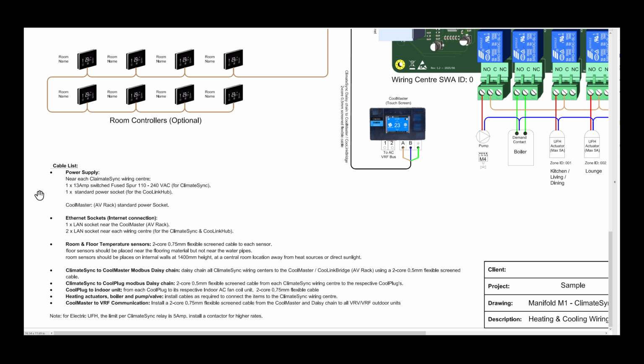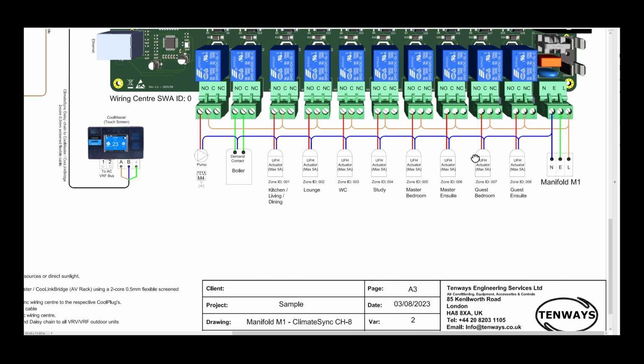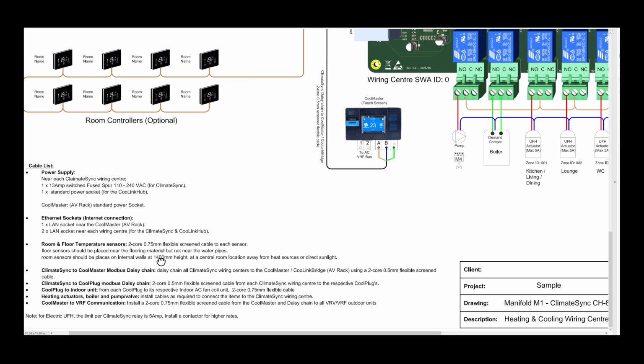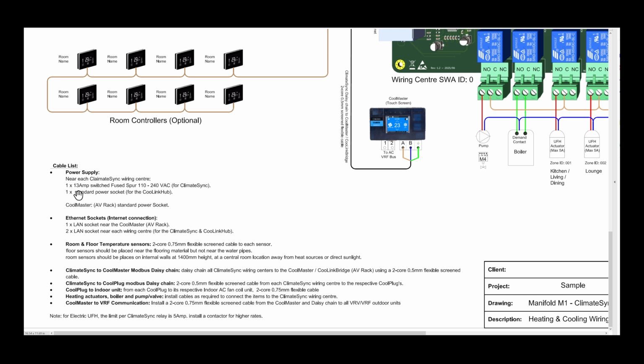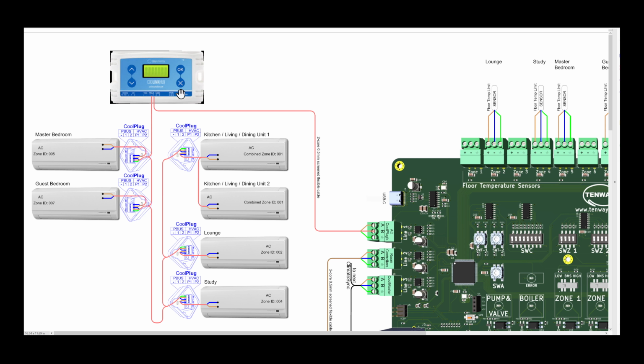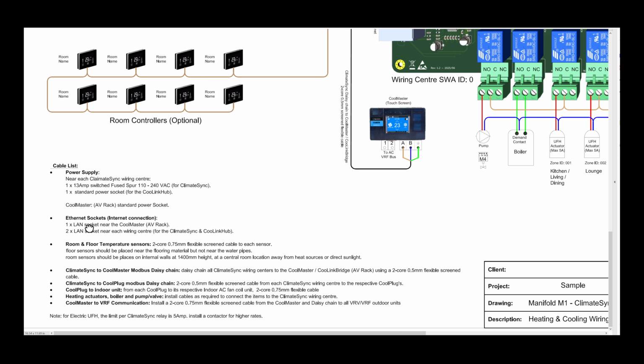So power supply, near each ClimateSync wiring center, you will have a power supply for the wiring center. Normally that would be a fuse spur near the wiring center, 110 to 240 volt for the wiring center, and that will connect as we showed right over here. The next one will be a 13 amp, a standard power socket, and that's for the CoolLinkHub. So this will be the CoolLinkHub that goes near the wiring center, and this uses a transformer which connects to the standard socket. The CoolMaster, which will sit at the AV rack, will also require a standard socket to use a transformer that connects and powers the CoolMaster.